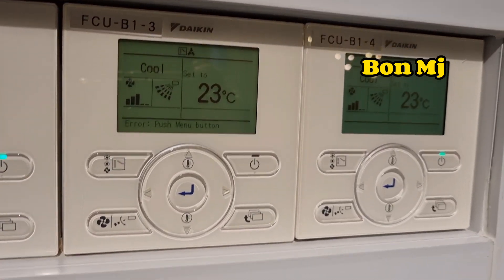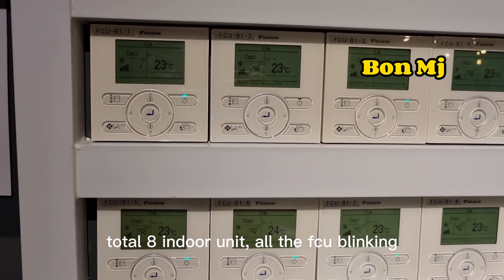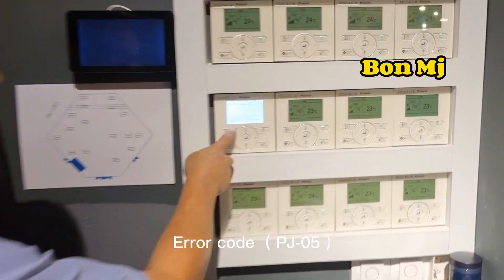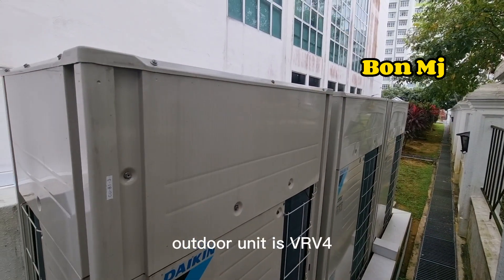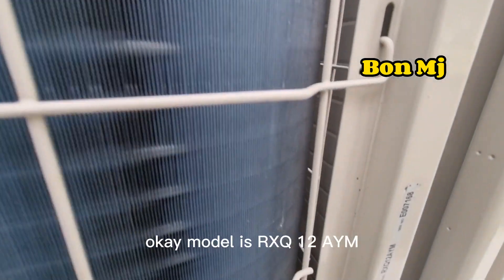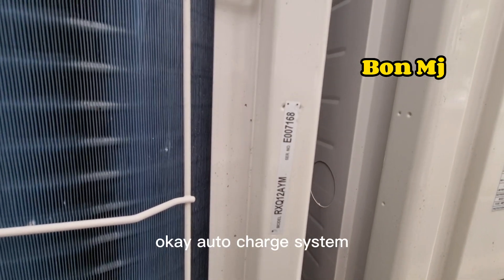Total eight indoor units, all the FCU blinking. Error code PJ-05. Outdoor unit is a VRV4. Model is RXQ12AYM. Auto charge system.